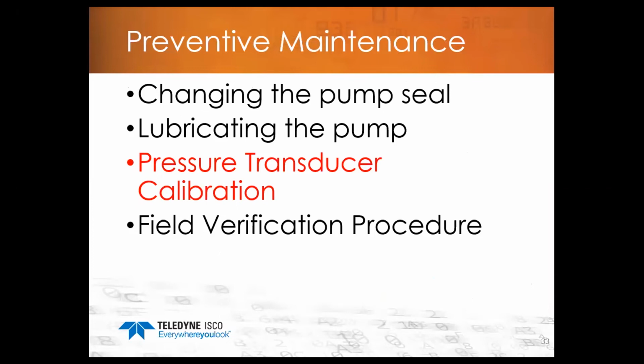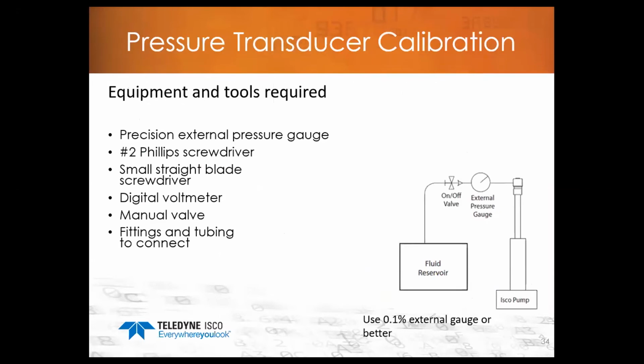Okay, the next step as far as preventative maintenance is concerned would be a pressure transducer calibration. Now, to do a pressure transducer calibration, you would have to have an external pressure gauge so that you can compare the pressure that the pump is at versus what the pressure on the controller is telling you. So you'll need a manual valve, a voltmeter, and an external pressure gauge.